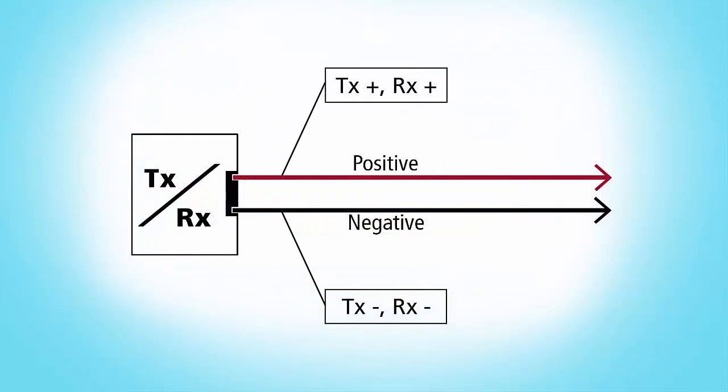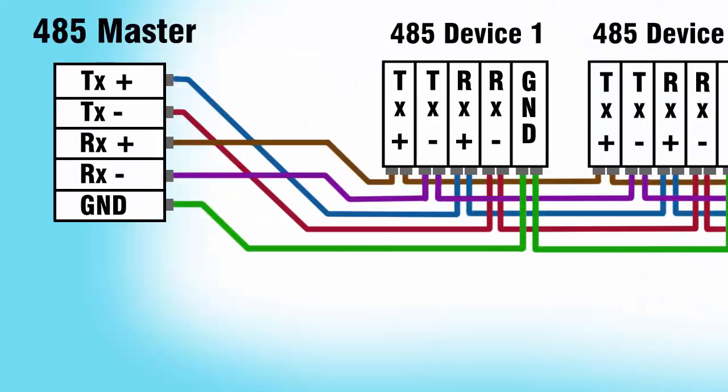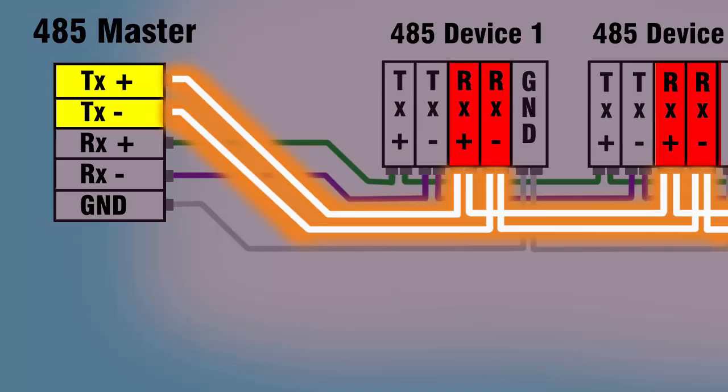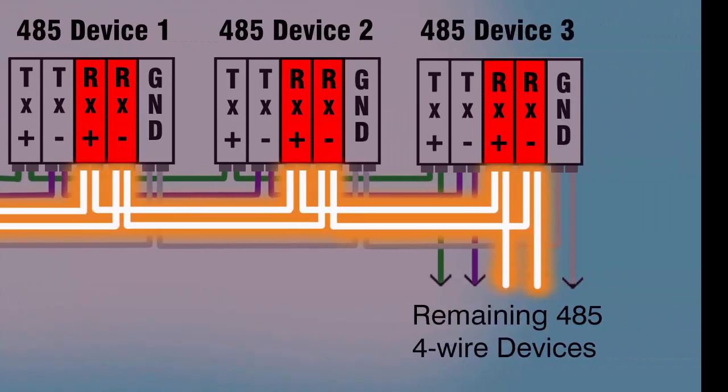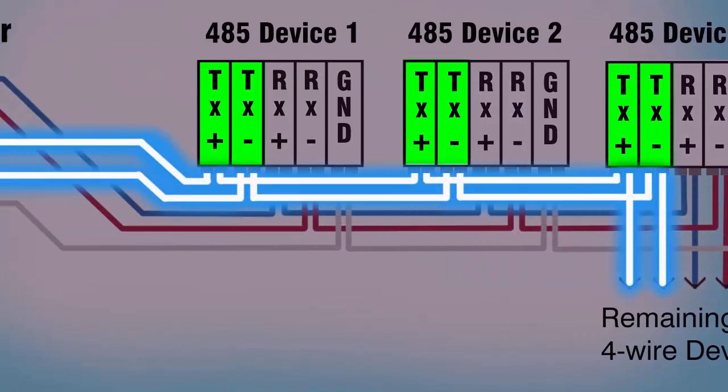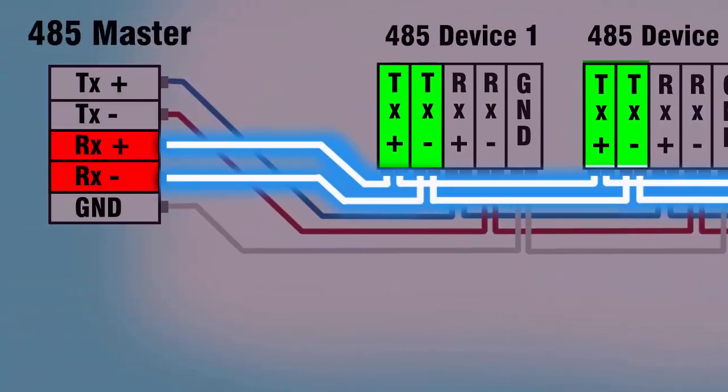In a two-wire network, the transmitter and receiver of each device are connected to a pair of wires, positive and negative. Four-wire networks have one master port with the transmitter connected to each of the slave device receivers on one pair of wires. The slave transmitters are all connected to the master receiver on a second pair of wires.